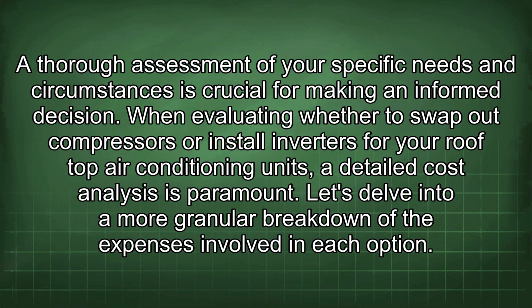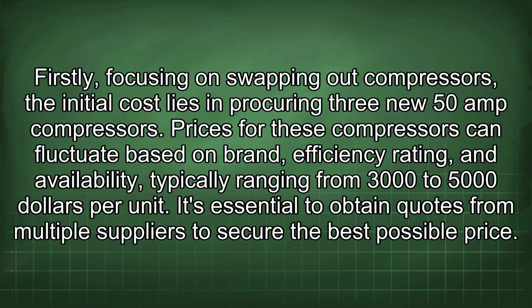When evaluating whether to swap out compressors or install inverters for your rooftop air conditioning units, a detailed cost analysis is paramount. Let's delve into a more granular breakdown of the expenses involved in each option. Firstly, focusing on swapping out compressors, the initial cost lies in procuring 3 new 50-amp compressors. Prices for these compressors can fluctuate based on brand, efficiency rating, and availability, typically ranging from $3,000 to $5,000 per unit. It's essential to obtain quotes from multiple suppliers to secure the best possible price.